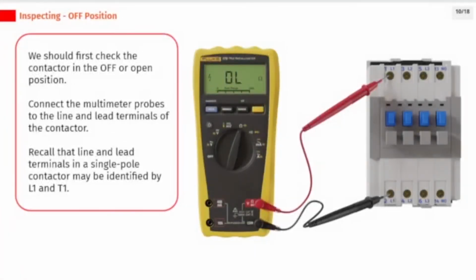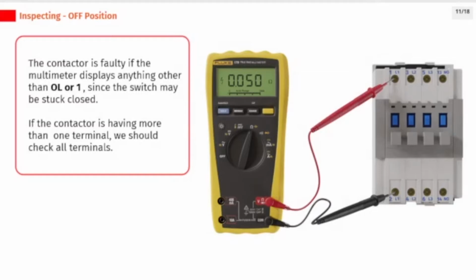We should first check the contactor in the off or open position. Connect the multimeter probes to the line and lead terminals of the contactor. Recall that line and lead terminals in a single-pole contactor may be identified by L1 and T1. The contactor is faulty if the multimeter displays anything other than OL or 1, since the switch may be stuck closed. If the contactor has more than one terminal, we should check all terminals.